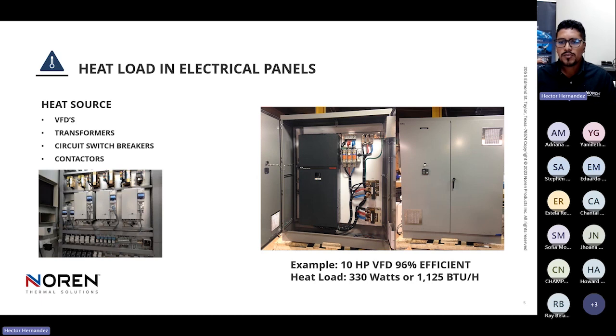Let's see an example. We have on the screen a VFD of 10 horsepower that is 96% efficient. The estimated heat load for this VFD is 330 watts, or 1125 BTU per hour. This is a huge amount of heat for an electrical panel and it can cause overheating.